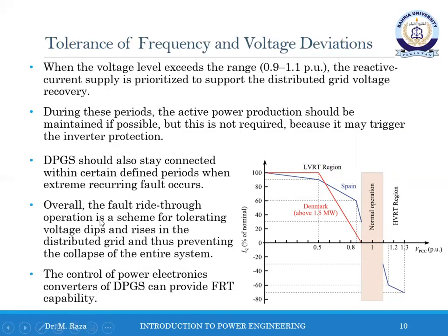According to Spanish grid codes, as illustrated with the blue line over here, if the voltage drops to 0.85 per unit, such as this point, then the distribution power generation system must inject reactive current up to 60% of its nominal current. In this case, the injection of active current is reduced. The amount of reactive current should be increased up to 80% if the grid voltage or PCC bus voltage drops to 0.5 per unit. If the grid voltage drops further, then the 100% reactive current must be injected by the distribution power generation system, such as here.